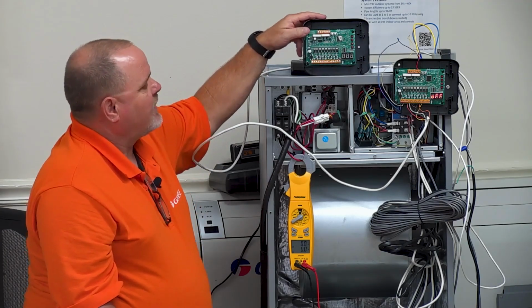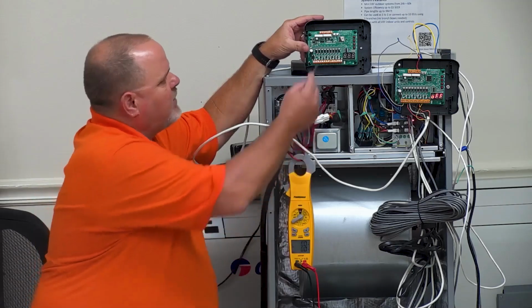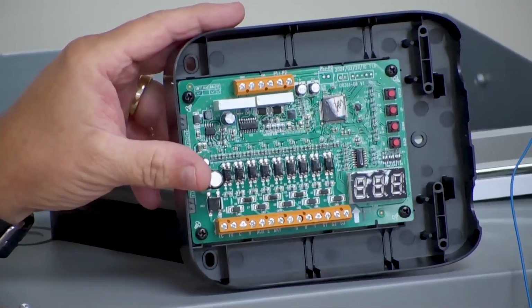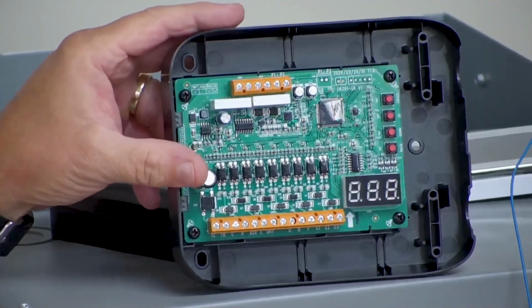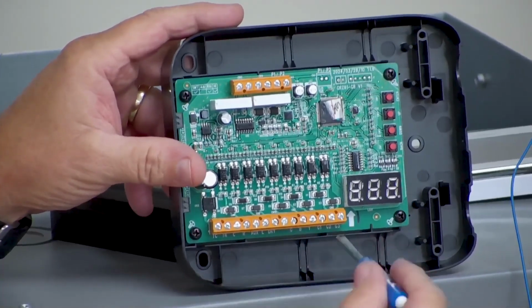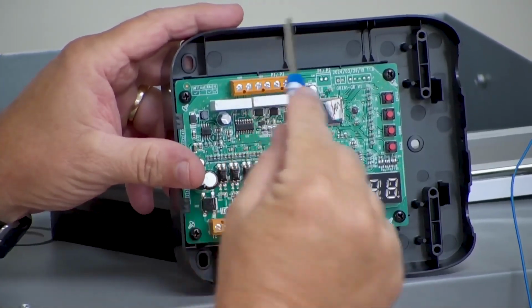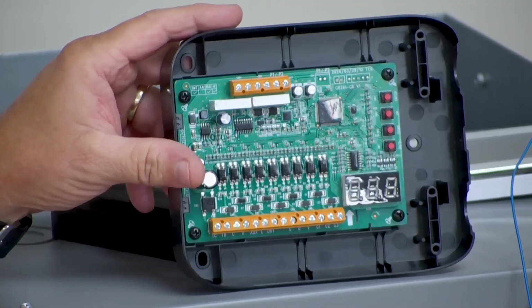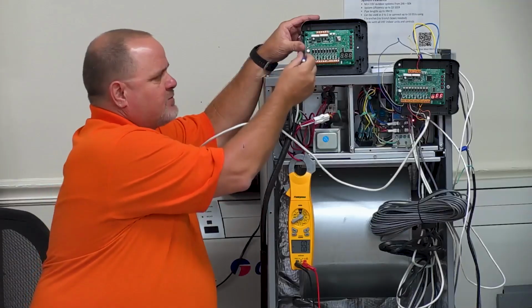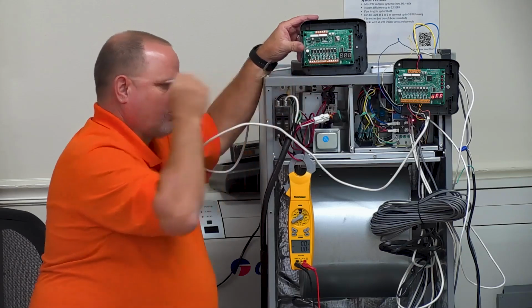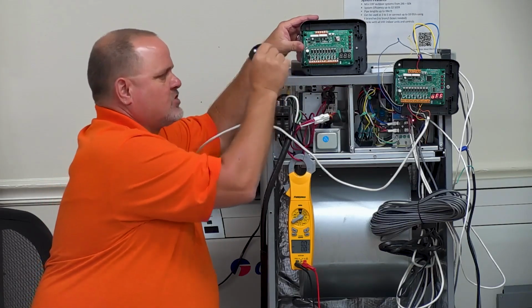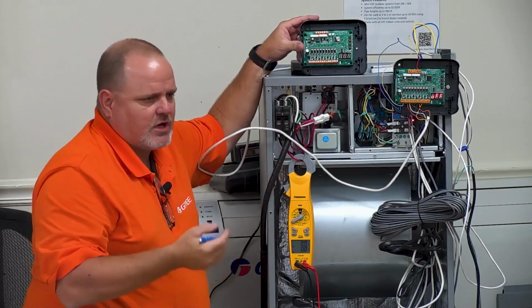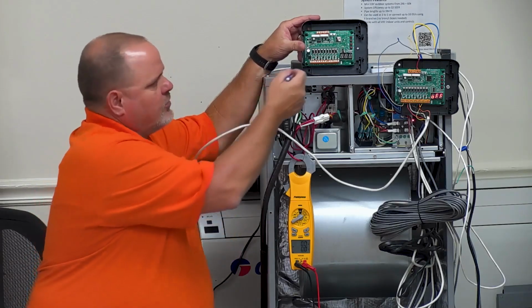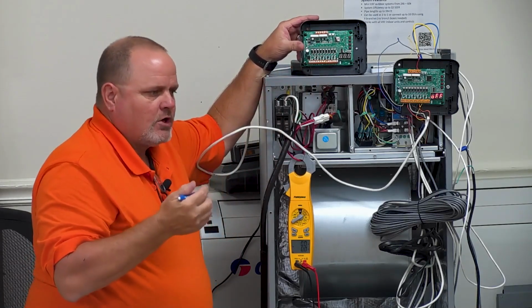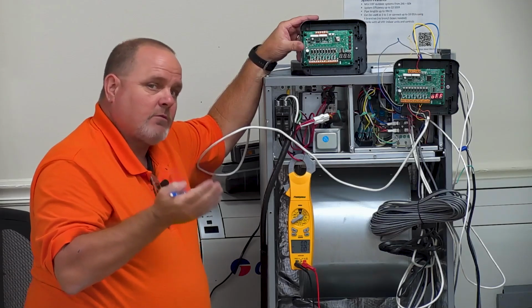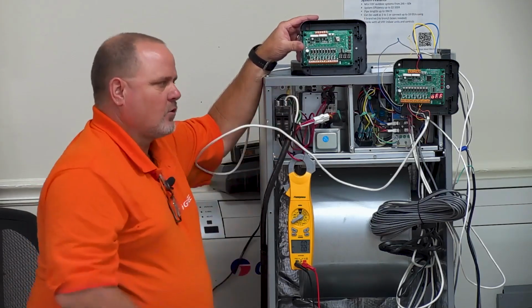And then the only other connections you're going to be making would be up here at the top, and I'm not going to worry about showing them to you. That's just going to be your H1 and H2. So basically what's going to happen is you hook up your thermostat and everything here. You take your H1, H2 wiring to your H1 and H2 on the air handler. So now this becomes your wired controller, but your thermostat's actually telling this what to do. This is telling the air handler what to do. So instead of using a GREE controller, you're using a GREE 24-volt adapter to transform that signal that you got from your thermostat to tell the air handler what to do.